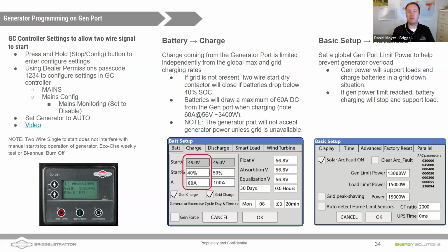To address your question earlier, you can adjust the rate at which you charge from a generator so as not to overload it. The point we're making is that if you do want to use a small generator, you can limit the gen power on the basic setup tab, advanced, and under the battery setup, you can limit how quickly you're charging off your generator. When your generator is running and the batteries are charging, the generator is the only thing supporting loads, and it's also the only thing charging your batteries, right? Technically, you could still have solar coming in to support that charging.